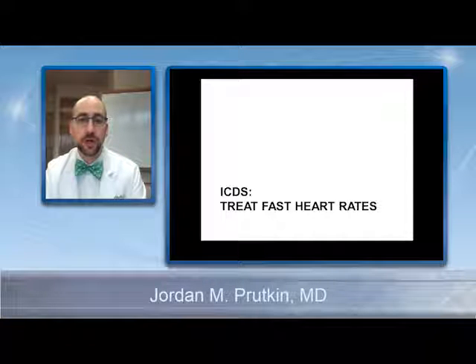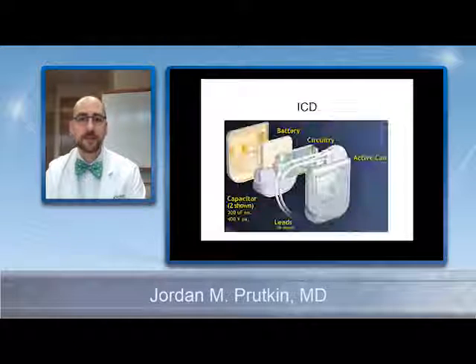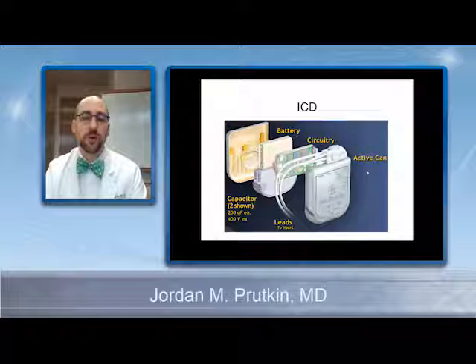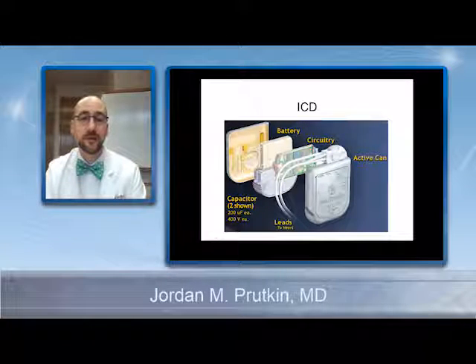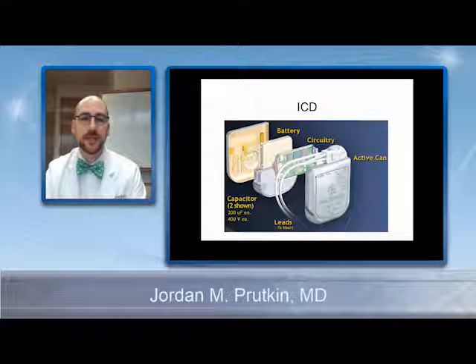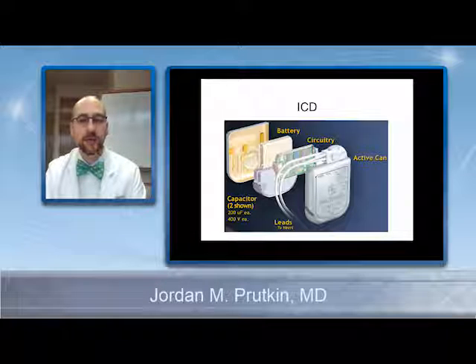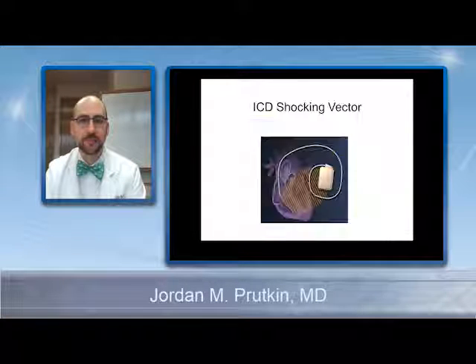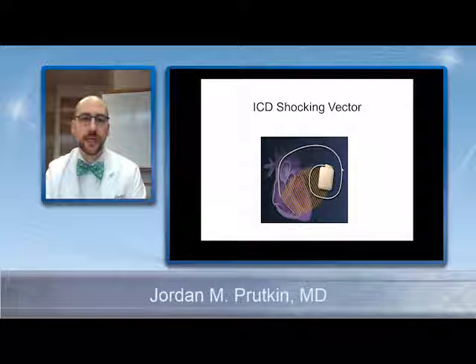ICDs, implantable cardioverter defibrillators or implantable cardiac defibrillators, treat fast heart rates. The way this device works is that you have your generator, and the difference between this generator or can compared to a pacemaker is it has to have both a different battery but also capacitors. So the energy comes from the battery and it's stored on the capacitor, and that allows the device to give a shock to get someone out of ventricular fibrillation or ventricular tachycardia.